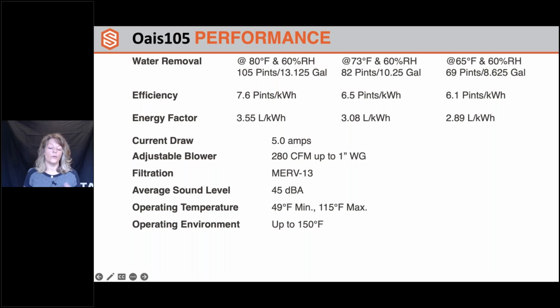Operating temps, so in spaces for the air going into the unit is 49 to 115. That's when we can still, if dew points allowing, and there's water there, we can remove some water at those conditions. Not very common, but I know that's a question we get often. And the operating environment is up to 150 degrees. So this can be installed in attics in the south. It will still operate with the external operating environment of 150 degrees.